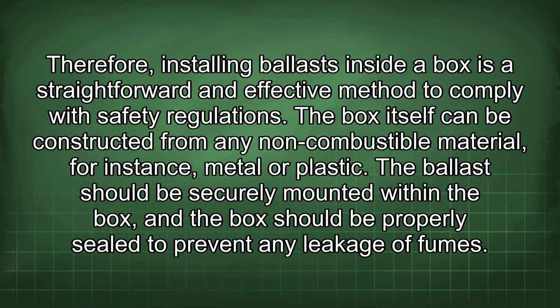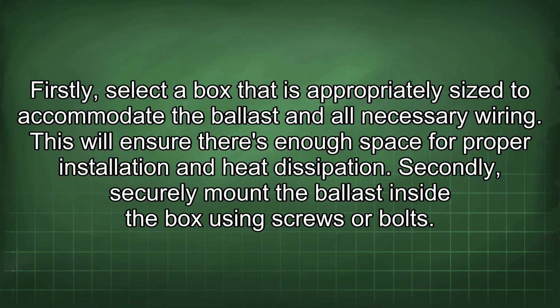The box itself can be constructed from any non-combustible material, for instance, metal or plastic. The ballast should be securely mounted within the box, and the box should be properly sealed to prevent any leakage of fumes. Firstly, select a box that is appropriately sized to accommodate the ballast and all necessary wiring. This will ensure there's enough space for proper installation and heat dissipation.